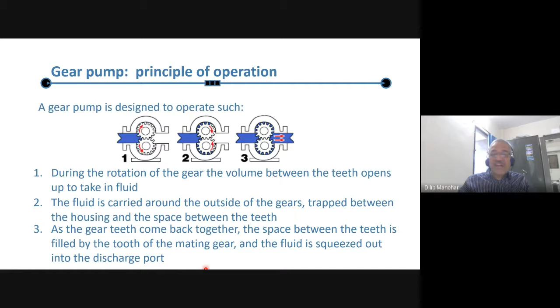So here we can go through a small calculation of gear pump design. Here it is shown that the displaced volume is the swept volume from the casing and gear. We will use a smaller unit, millimeter cube per revolution. For one gear turn, one gear tooth and gap, this gap passes from this side to this side. For one gear tooth, how much is the gap? One half, since we are considering one side, of pi by 4 into DO square minus DI square, that is the gear OD square minus the root diameter square. This is the volume swept in one turn.